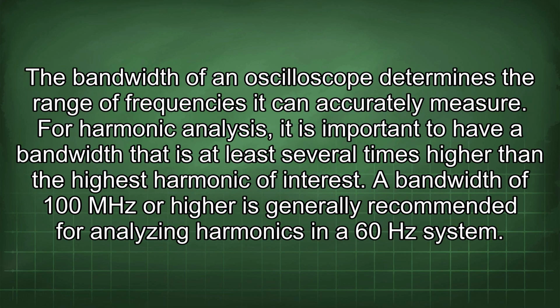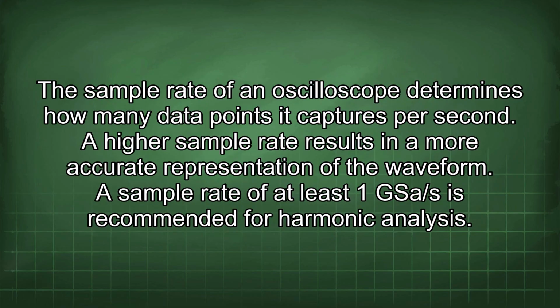The bandwidth of an oscilloscope determines the range of frequencies it can accurately measure. For harmonic analysis, it is important to have a bandwidth that is at least several times higher than the highest harmonic of interest. A bandwidth of 100 MHz or higher is generally recommended for analyzing harmonics in the 60 Hz system. The sample rate of an oscilloscope determines how many data points it captures per second. A higher sample rate results in a more accurate representation of the waveform. A sample rate of at least 1 GSa/s is recommended for harmonic analysis.